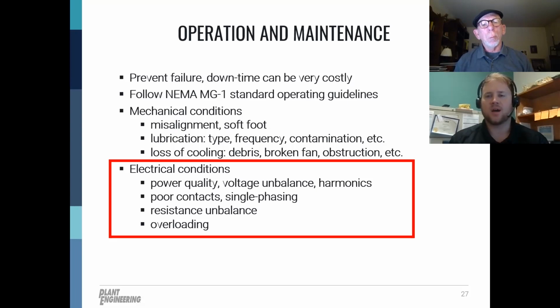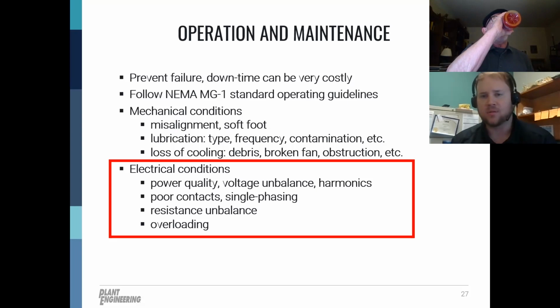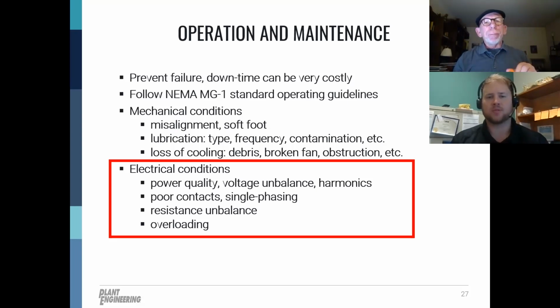If the motor is hot, if the motor's been running, you've been operating, and you wanted to compare those winding resistances to, say, original manufacturer values, most manufacturers will supply those when you buy a new motor. Then just let the motor cool down, and then you'll have a good apples to apples comparison. If you are running these electrical checks with these tools and you do see some resistances out of balance, then you may want to do a little bit more, deeper diagnostic check with a dielectric test or a Megger or something like that.